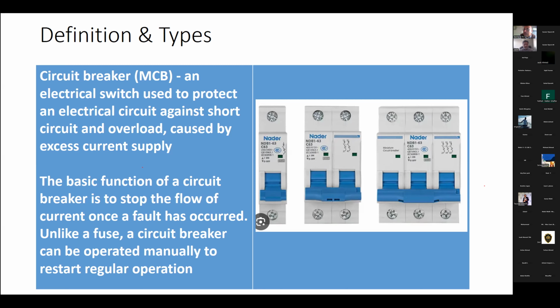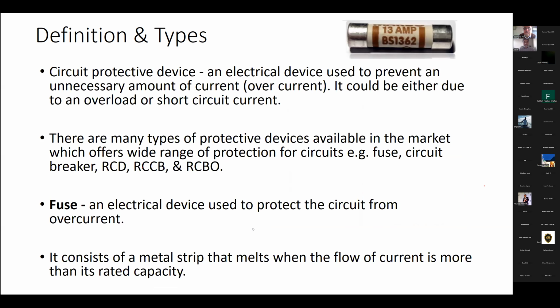And in the case of a short circuit, it's not necessarily that just more than 63 ampere will flow and then it will trip. No, when there is a short circuit, the amount of current is maybe in the hundreds. And there is a very strong chance that if our protective device does not work and there is a short circuit, there will be a fire. So this is what you need to remember: protective devices are very important. If we go back, let's say 15 or 20 years, initially our consumer unit had only fuses. Then they changed fuses to circuit breakers. Then from circuit breaker they came to RCD, from RCD to RCCB, then RCBOs.